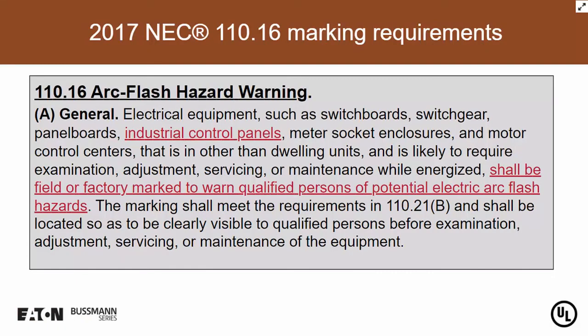And so let's take a look at what the code talks about. The National Electrical Code basically says, 110.16, arc flash warning labels: In general, electrical equipment such as switchboards, switchgear, panel boards, industrial control panels, meter socket enclosures, and so on, shall be field or factory marked to warn qualified persons of potential electrical arc flash hazard. Right? That's the National Electrical Code. And then NFPA 70E basically states that we put an arc flash label on the panel on what PPE that we need to wear and so on.